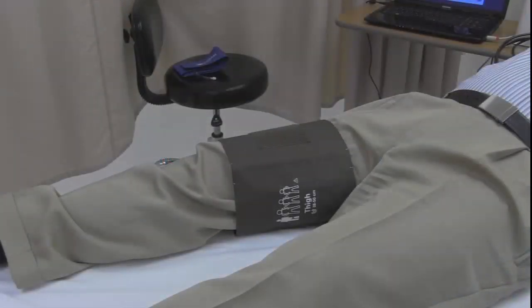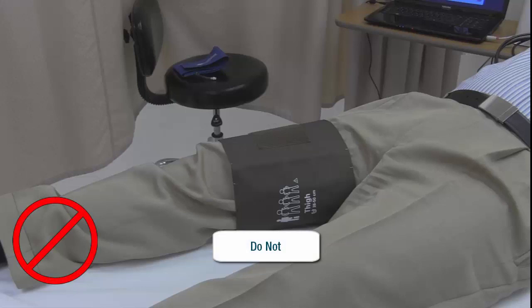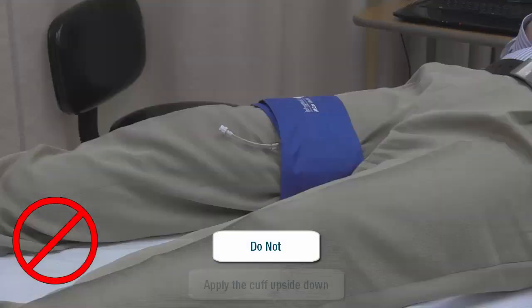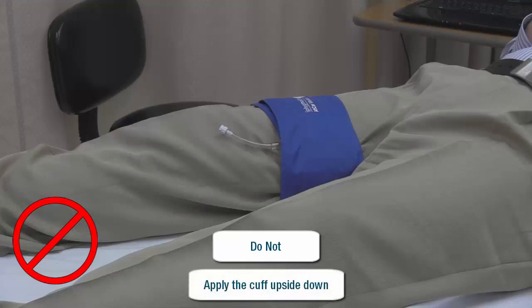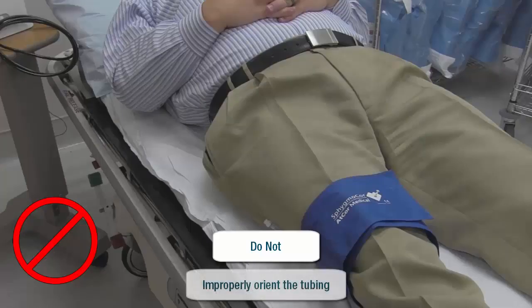Proper cuff application is important for ensuring high-quality data capture. Take caution to not use any cuff other than the light blue thigh cuff. Do not place the cuff upside down. Do not orient the cuff so that the tubing is anywhere other than the top of the thigh.